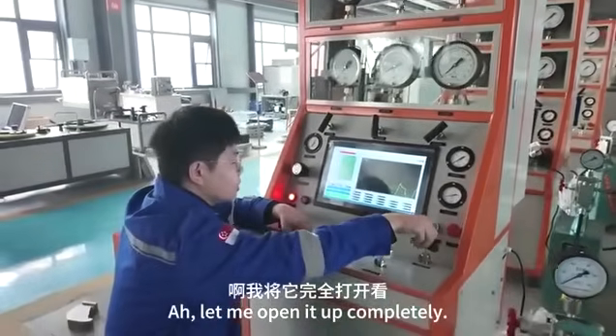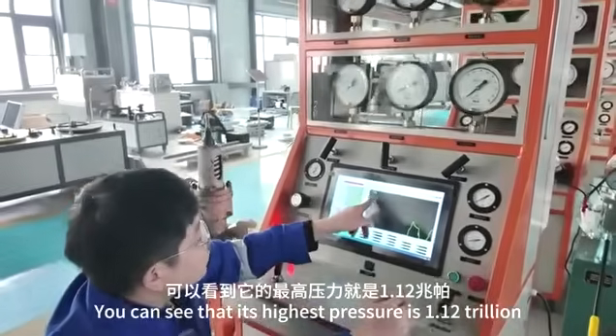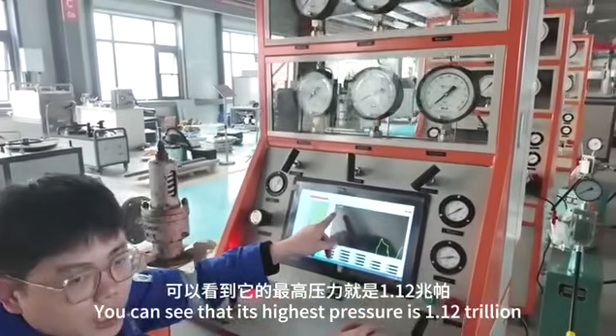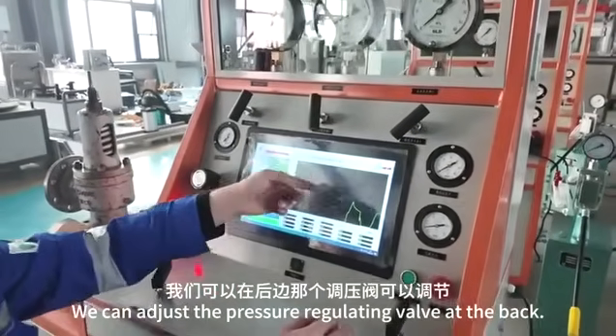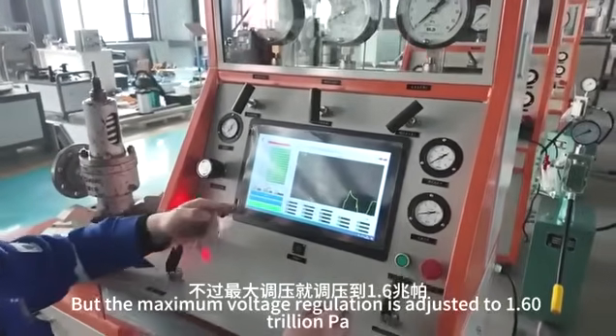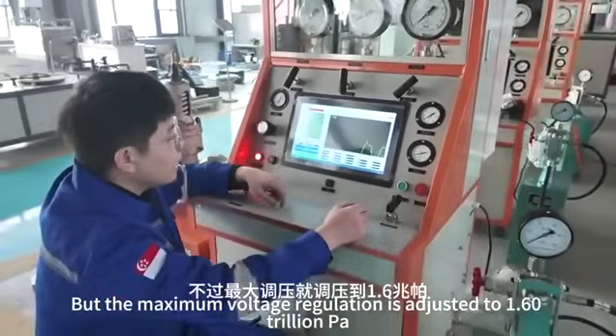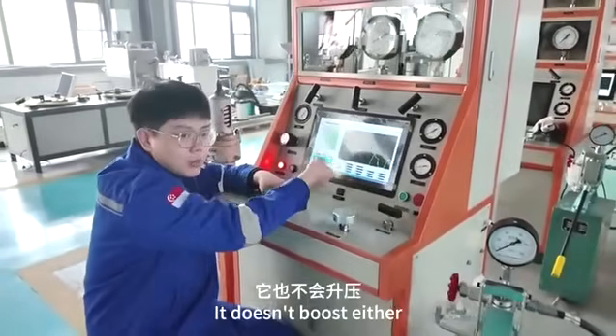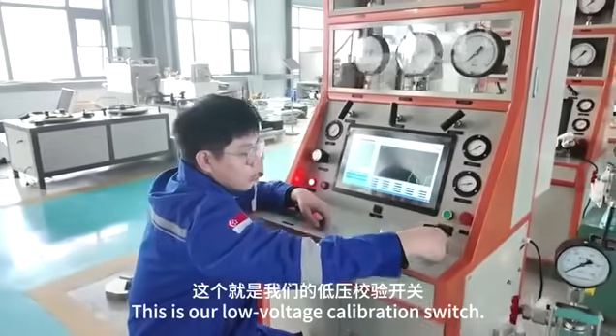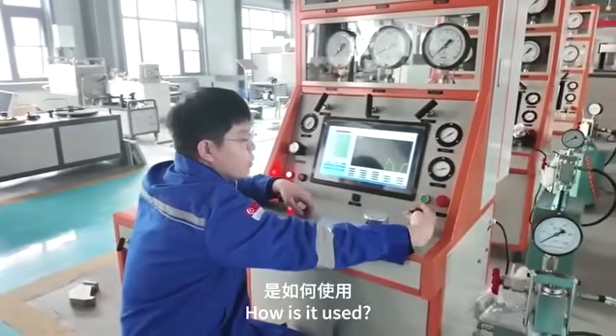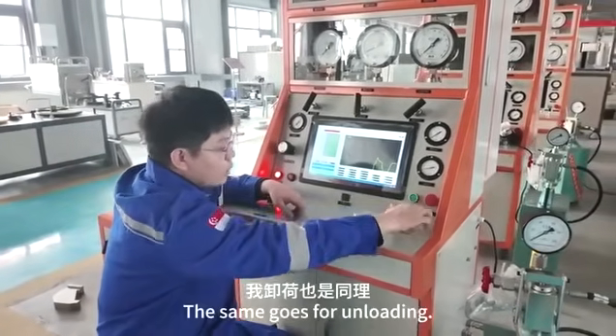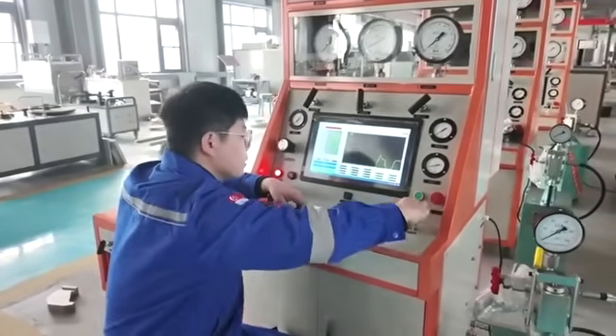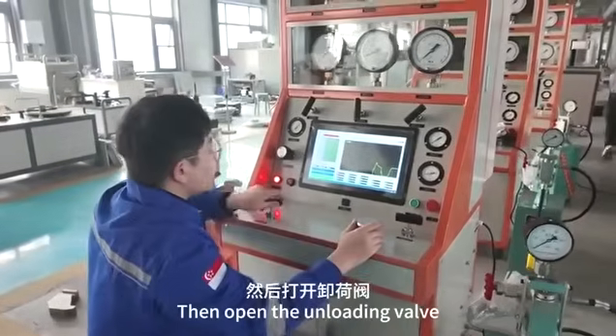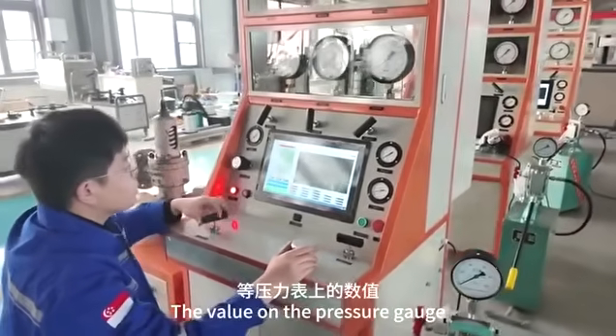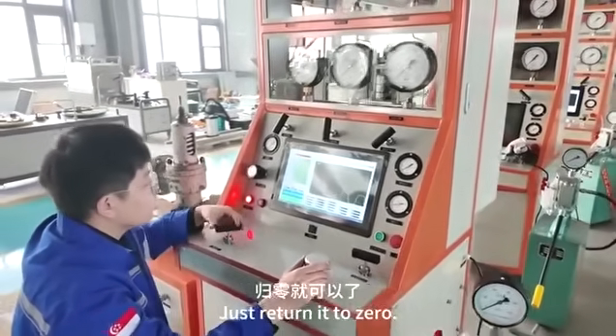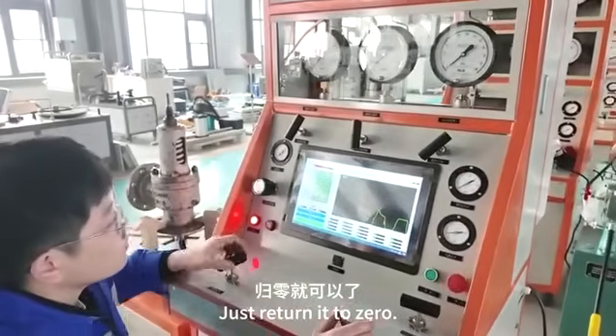Let me open it up completely. You can see that its highest pressure is 1.12 MPa. We can adjust the pressure regulating valve at the back, but the maximum pressure regulation is adjusted to 1.60 MPa. And you see, I opened it up completely. It doesn't boost either. This is our low voltage calibration switch. How is it used? The same goes for unloading. Turn it off, then open the unloading valve. The value on the pressure gauge just returns to 0.